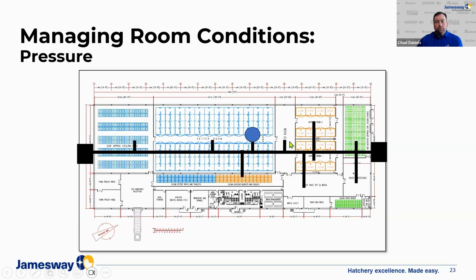Oftentimes we see hatcheries where the reference for this room has a tube that runs out of the side of the building over here, and the setters have a tube that runs out of the front of the building over here, and the wind is coming from a certain direction. And as a byproduct, you don't have consistency in controlling pressure between those two rooms because of two different outside air references. So this is the first key to having good pressure control: having this one reference conduit throughout your facility.